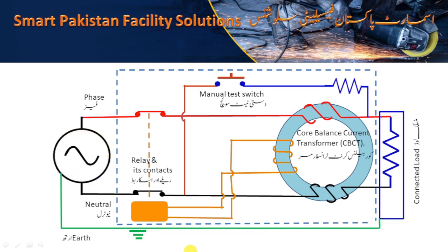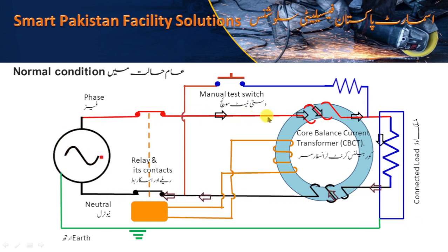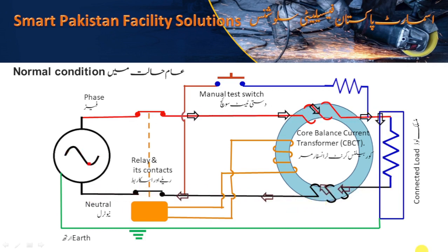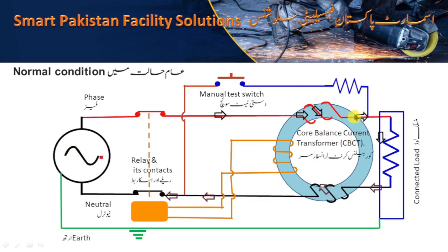Let us see how it works. The first scenario is normal working condition, in which everything works fine and there is no fault in the load. After switching on the power supply, current will start to flow from the phase wire to the load and return through the neutral towards the source. In this case, the current entering from the phase conductor will be equal to the current leaving from the neutral conductor, but the direction of both will be opposite.